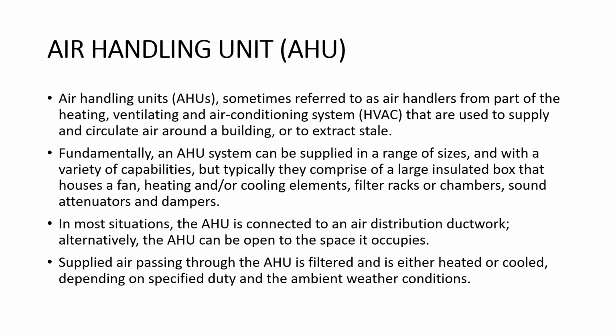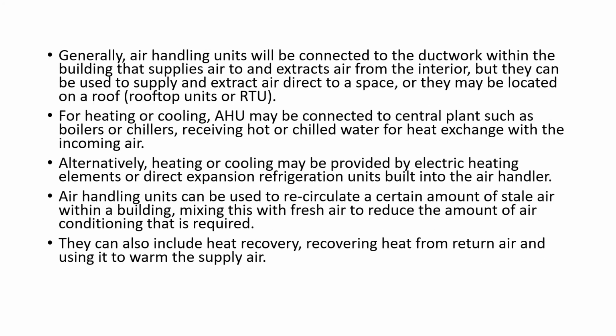In most situations, the AHU is connected to an air distribution ductwork. Alternatively, the AHU can be open to the space it occupies. Supplied air passing through the AHU is filtered and is either heated or cooled depending on specified duty and the ambient weather conditions. So basically, air handling units will be connected to the ductwork within the building that supplies air to and extracts air from the interior, but they can be used to supply and extract air direct to a space, or they may be located on a rooftop unit, or RTU.